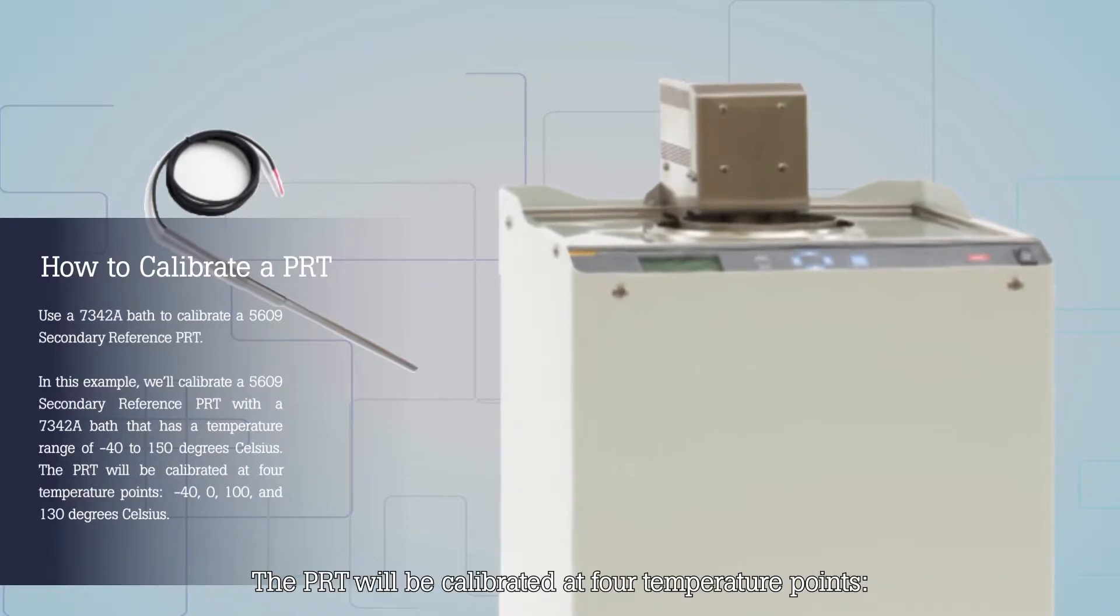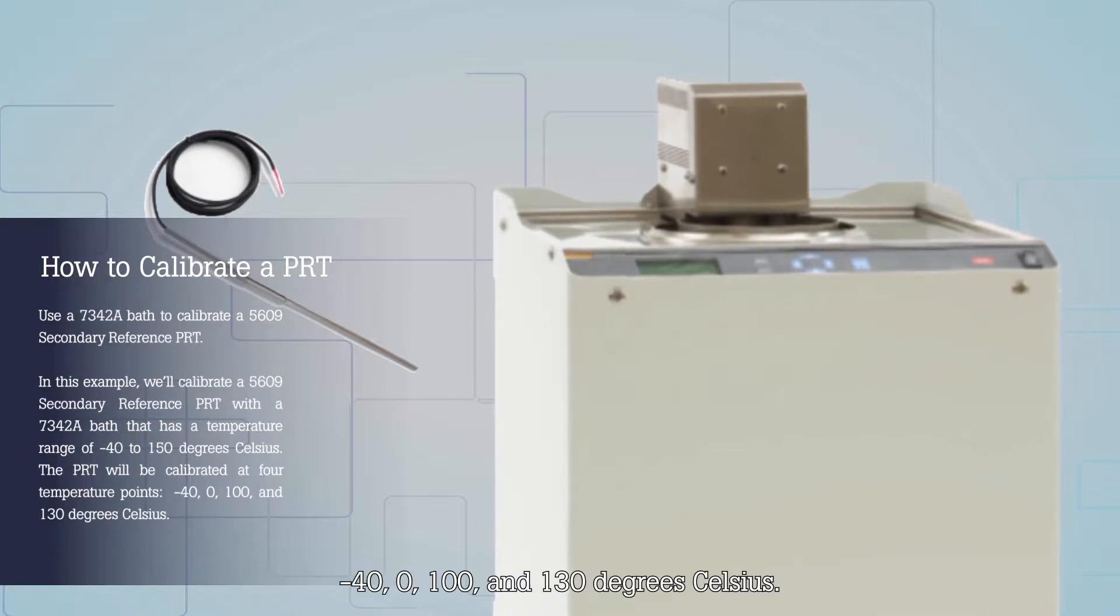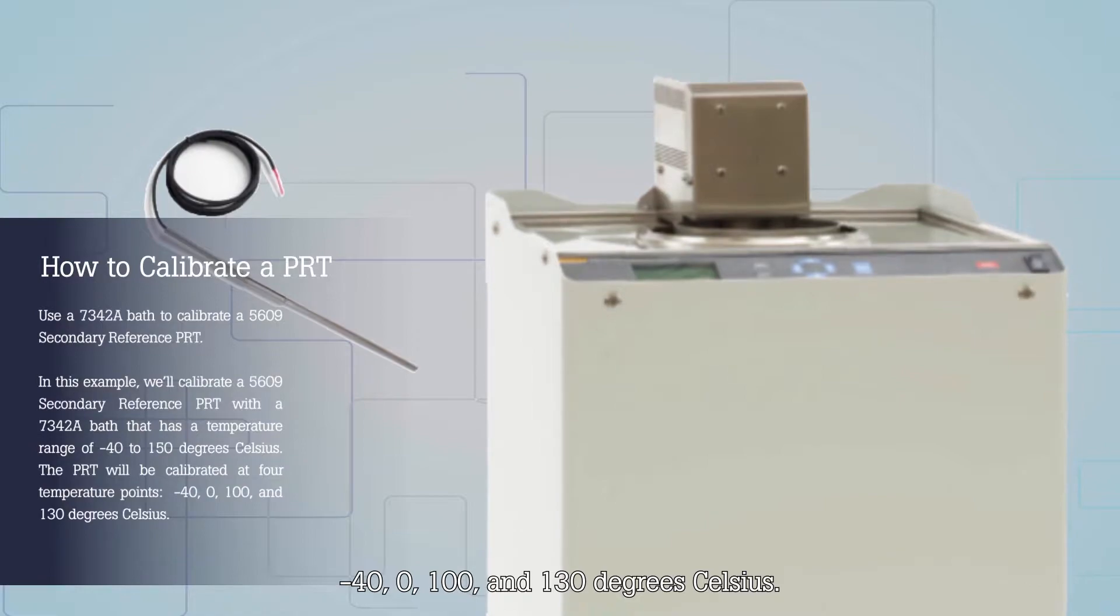The PRT will be calibrated at four temperature points: minus 40, 0, 100, and 130 degrees Celsius.